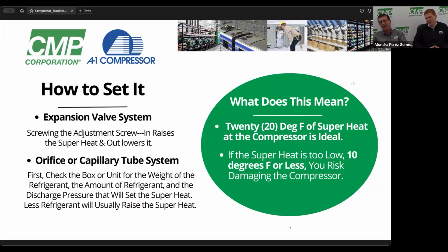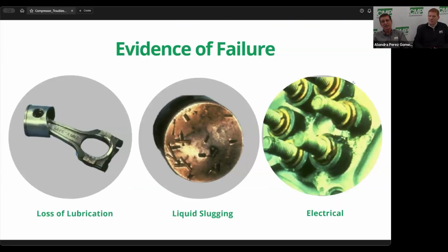Maybe, if I could get into a little bit on the air conditioning field, where it ices back, and in the air conditioning field, of course, everybody knows if it runs short of refrigerant or ices back on the compressor, that it floods and damages the compressor. But, trying to think of where I was going with that. Well, in low temp applications, you may see that. Yeah. Well, too, also, I've had where they change the compressor out and the system has a small leak in it, and then it'll leak down, and about a week or two or a month later, it'll flood back, ice the compressor back, flood back, tear the compressor up again. And then they just get a warranty compressor to put in there, and they just go to the system and charge it up. And then he still doesn't realize he's got a small leak. And then about a month later, it tears the second compressor up. Yep. And he's going to think he's got a sorry compressor, but actually what he's got is a little leak, and he just hadn't found the leak yet.